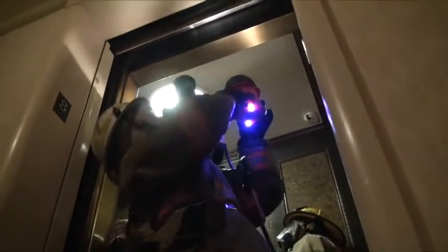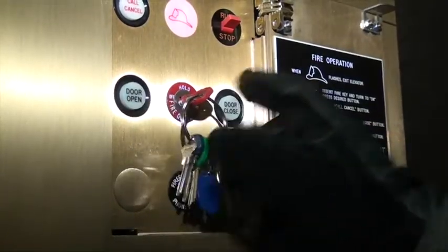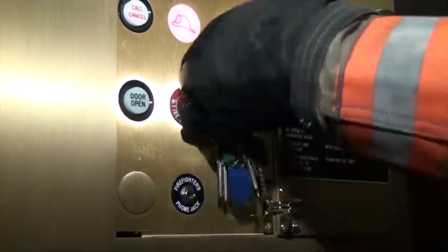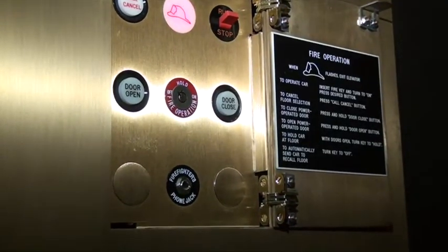If there is no smoke, check the hoistway for smoke and fire and the floor for orientation. Once at the desired floor, turn Phase 2 elevator control off and send the elevator keys back down with the car. Place the keys on the floor or in the corner by the elevator controls. Holding the elevator at the floor will prevent crews in the lobby from recalling it.